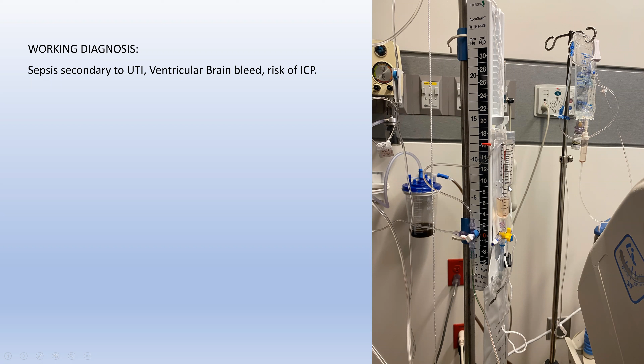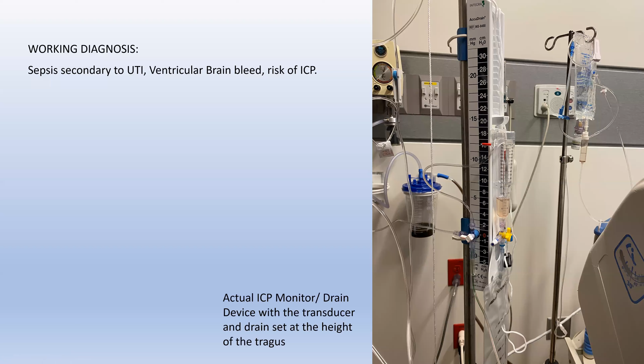This also connects, if you see this line right here, over to the transducer, which is how we would then, depending on where this is, if this is shut off to here, we're getting ICP monitor values. If it's shut off to here, it's draining. Again, it's one or the other. And again, just like I said, it acts kind of like a blow-off valve. And that's how it was placed.